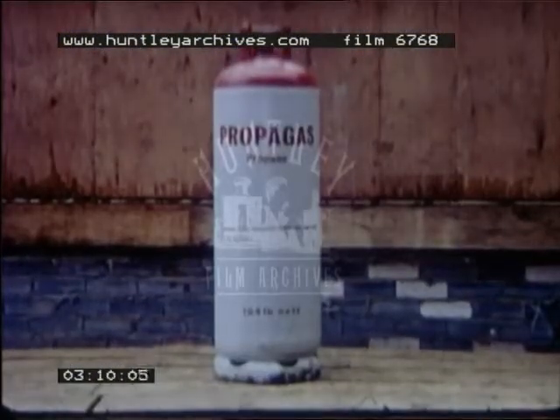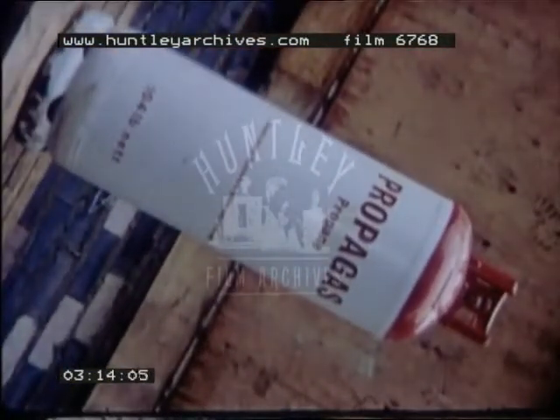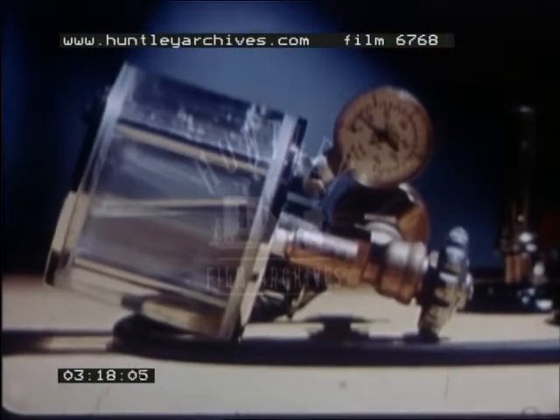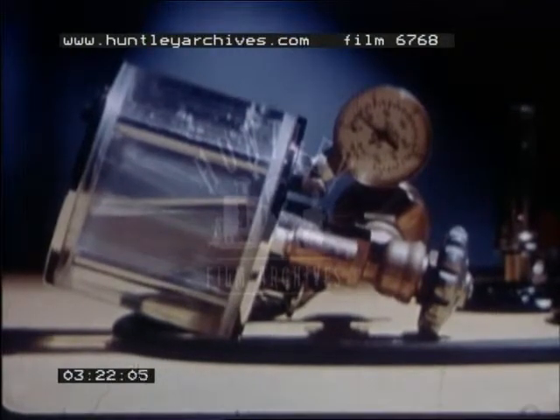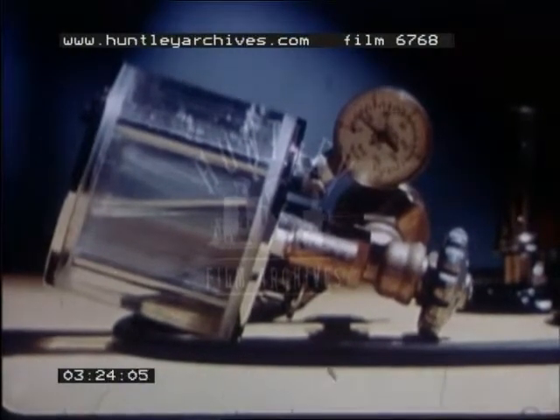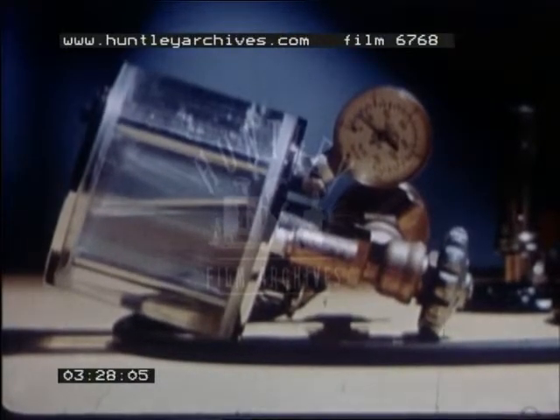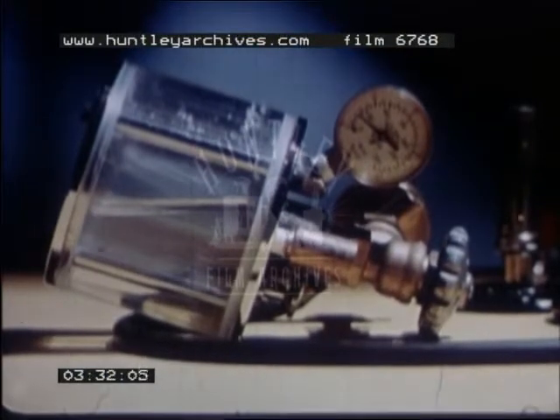Stand the cylinder upright on a firm foundation. Never use or store a cylinder on its side. As the Perspex container shows, it is possible in this position to draw off liquid instead of gas. A liquid leak is 250 times worse than a gas one, and any appliance which is designed to operate on gas will be quite incapable of coping with liquid, and a flare-up will result.